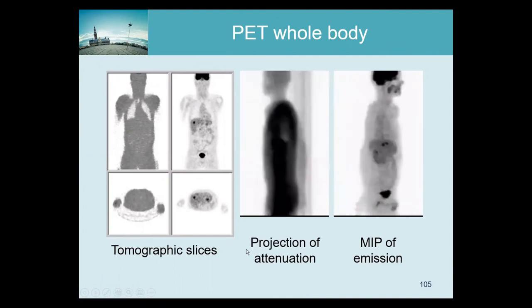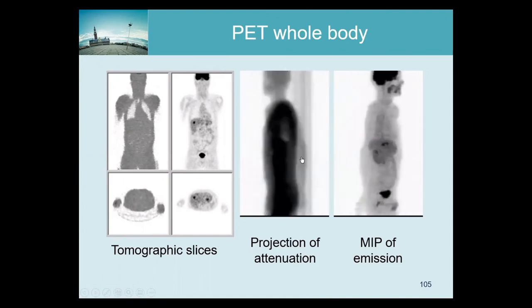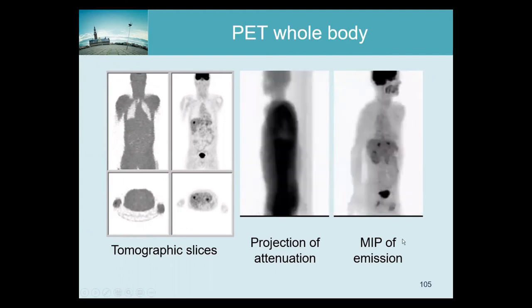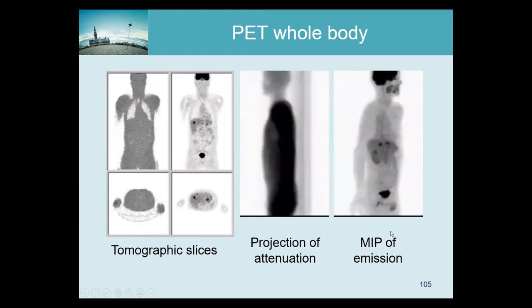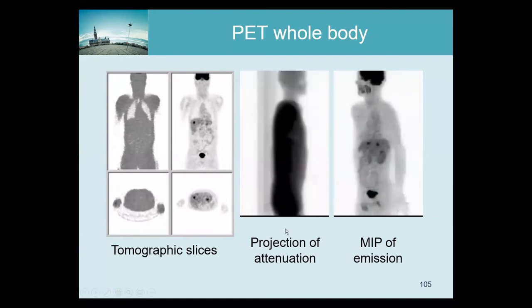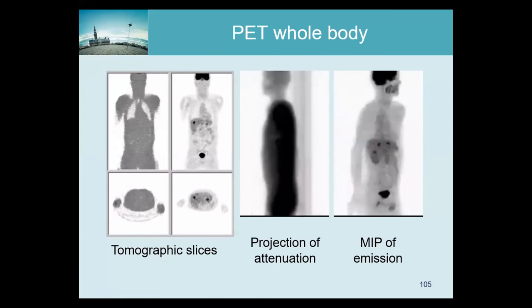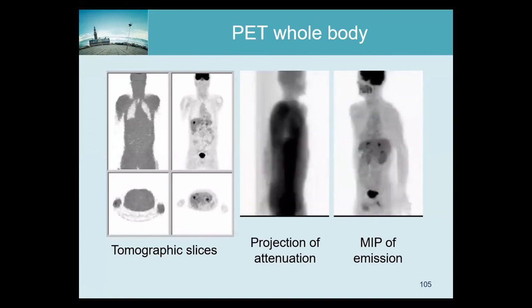Here are the final results with intensity indications to give an idea of image quality. You can see the typical quality of the activity images, and this is what you get when you estimate the attenuation from the transmission data. It looks very similar to what we see these days when we estimate attenuation values from the TOF data themselves — similar resolution, similar noise, and similar quality of the attenuation images.